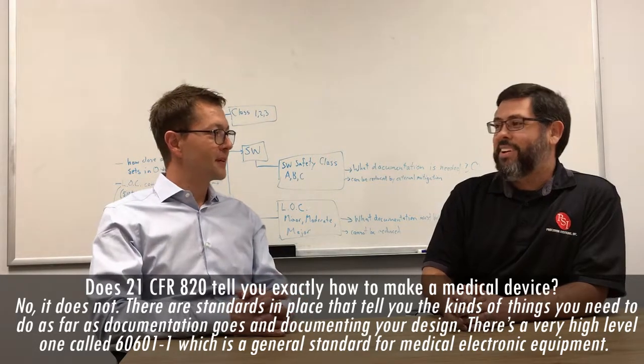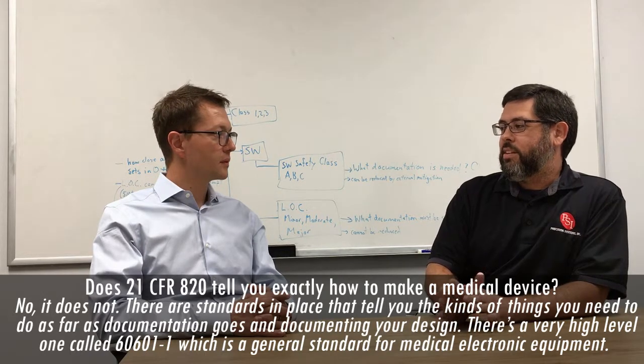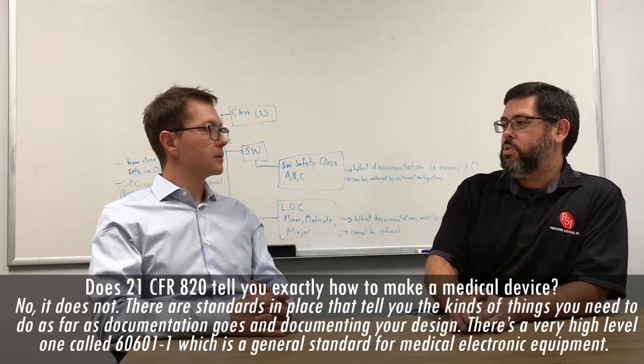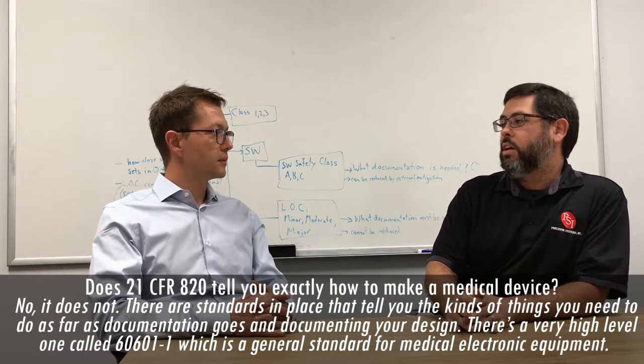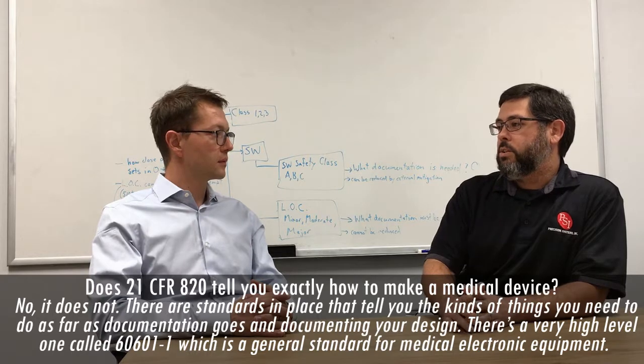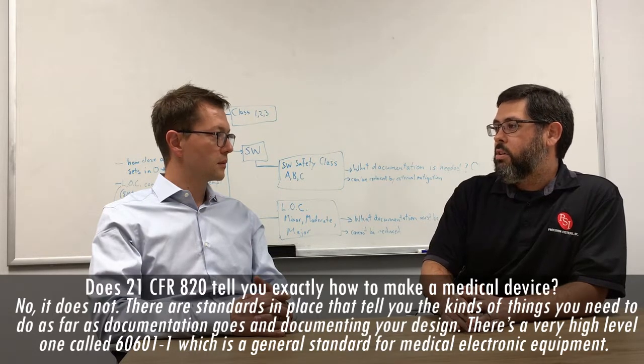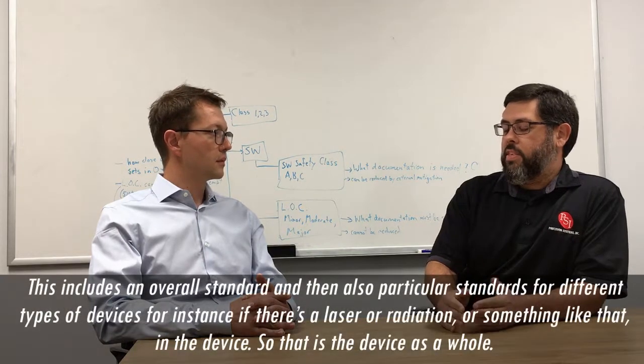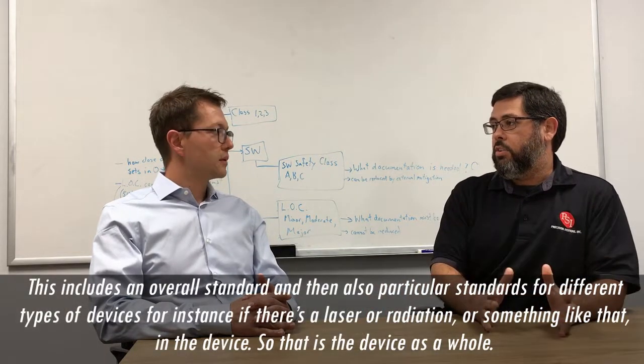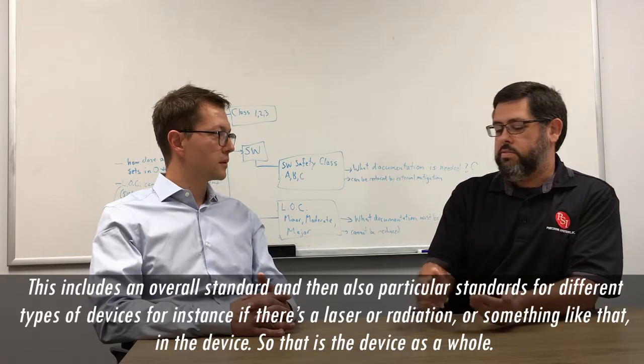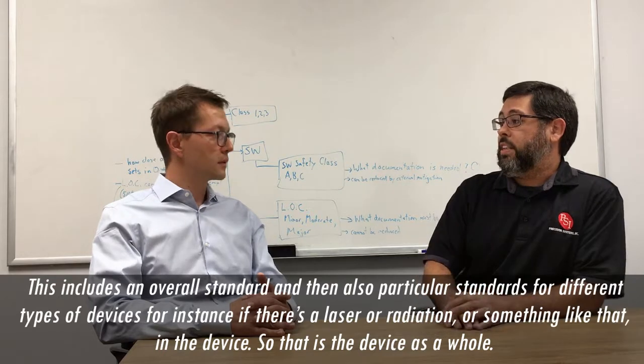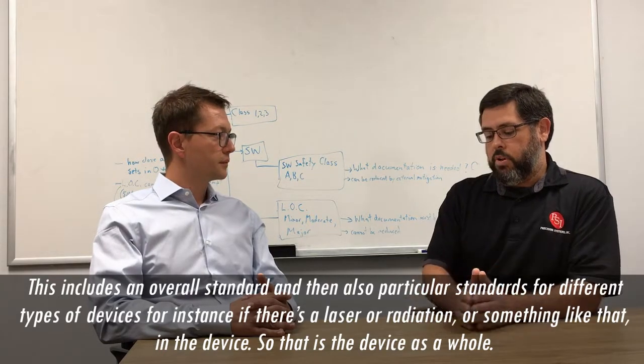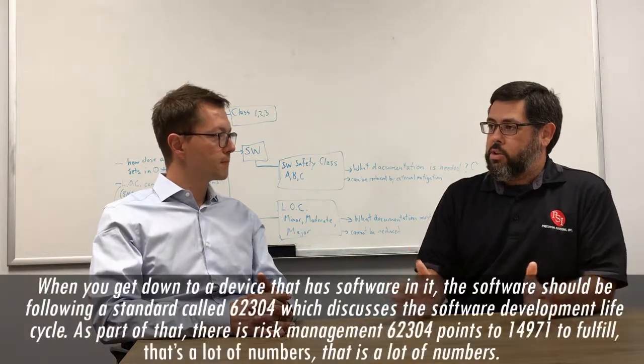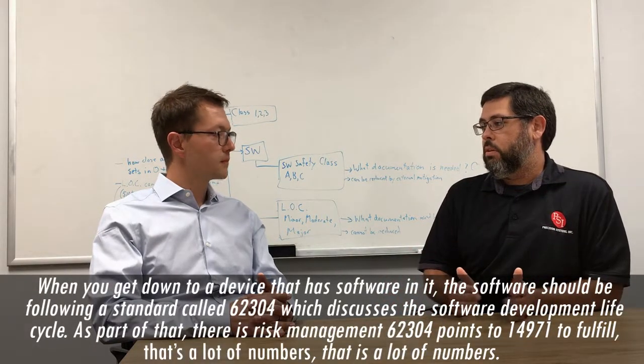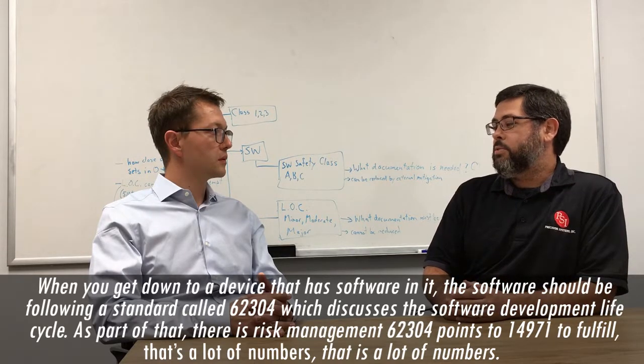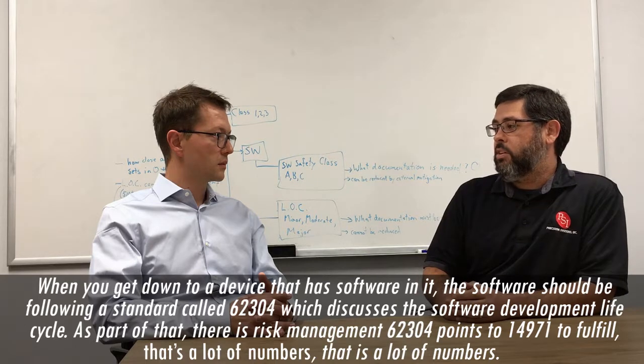So does 21 CFR 820 tell you exactly how to make a medical device? No, it does not. There are standards in place that tell you the kinds of things you need to do as far as documentation goes and documenting your design. There's a very, very high level one called 60601-1, which is a general standard for medical electronic equipment. This includes an overall standard, and then also particular standards for different types of devices, for instance, if there's a laser or radiation or something like that in the device. Okay. So that is the device as a whole. When you get down to a device that has software in it, the software should be following a standard called 62304, which discusses the software development life cycle.